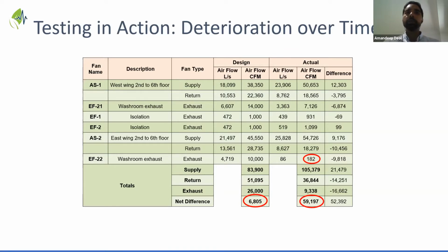This represents the 2 air handling systems with their respective exhaust fans and their return fans. They're serving the patient care tower, 2nd to the 6th floor. So originally the design, we put both the liters per second and CFM. The original design on the supply side for AS1 and AS2 was around 38 to 45,000. But when they measured the actual flows on both systems, the supply is actually running higher, around 50,000 to 54,000. And similarly on the return side, they were designed for 22,000. They're running lower, around 18,000.